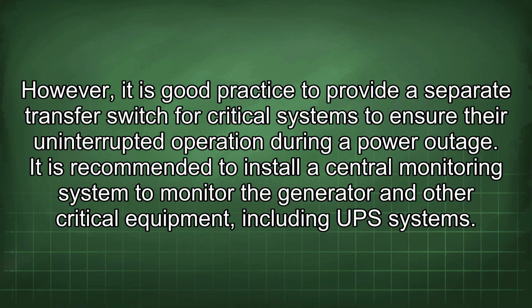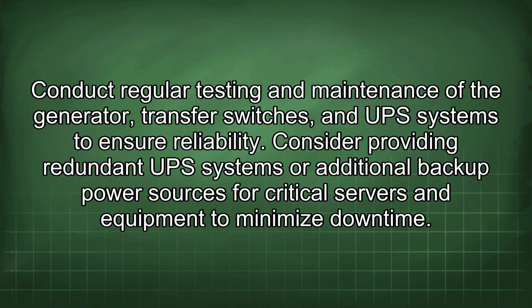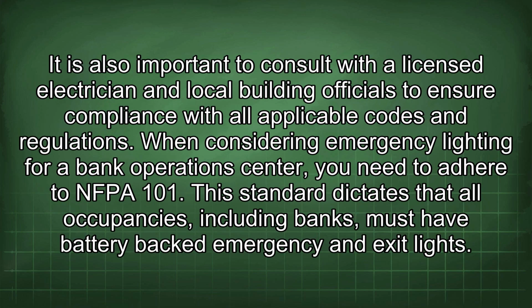It is recommended to install a central monitoring system to monitor the generator and other critical equipment, including UPS systems. Conduct regular testing and maintenance of the generator, transfer switches, and UPS systems to ensure reliability. Consider providing redundant UPS systems or additional backup power sources for critical servers and equipment to minimize downtime.